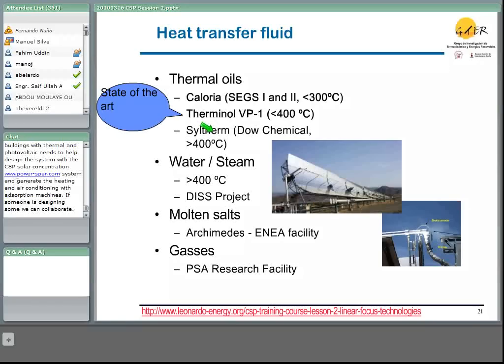There have been some experiences. So thermal oil as heat transfer fluid is currently the state of the art, but thermal oil, especially Therminol VP1 and similar oils, have some problems. Of course, the main problem is that they cannot operate at temperatures higher than 400 degrees C. Another problem is the cost, relatively expensive, not as much as Syltherm oil, but still expensive. And finally, in case of leaks they are pollutants, and because they operate at very high temperatures, they can burn, they can catch fire. So there are some environmental concerns about the use of this oil.